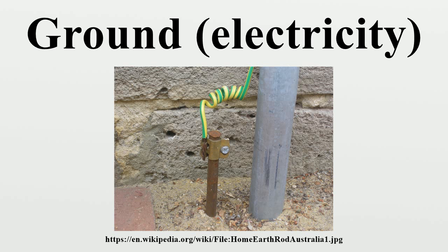In a mains electricity wiring installation, the term ground conductor typically refers to three different conductors or conductor systems, as listed below. Equipment earthing conductors provide an electrical connection between non-current carrying metallic parts of equipment and the earth. According to the U.S. National Electrical Code, the reason for doing this is to limit the voltage imposed by lightning, line surges, and contact with higher voltage lines. The equipment earthing conductor is usually also used as the equipment bonding conductor.